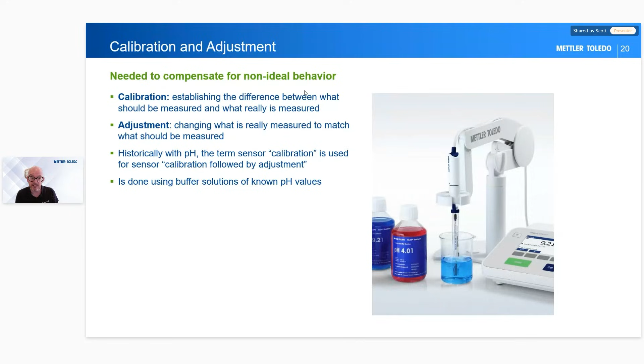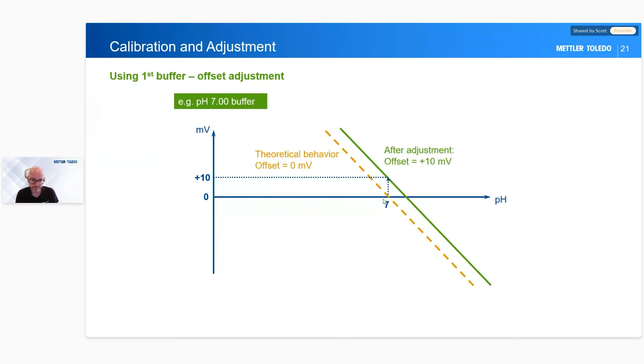So the first thing we do is we use a known buffer. In this case, we're using pH 7. We put it in and take our calibration, and it corrects the curve by giving us an offset. So this offset is 10 millivolts, either 10 millivolts to the left or up, and it moves by 10 millivolts away. So we know our pH 7 should be 0, but when we've put it in and taken a measurement, it actually reads 10 millivolts. The next bit is we then use a second buffer to give us a slope.